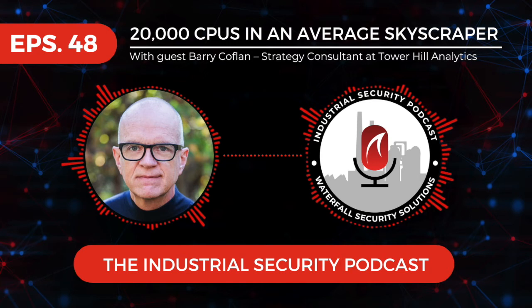It's actually very serious. They'll use the default IP address. They'll use the default passwords. They will put these embedded Linux controllers not necessarily behind the firewall. They will put them on the internet and not even know they're doing it. So this is a serious problem, and this exists in the industry today.